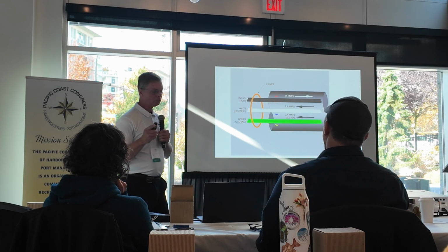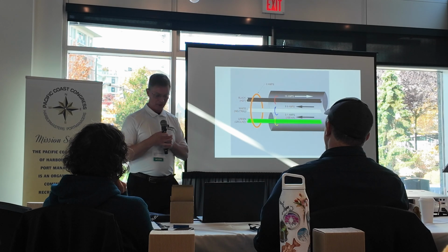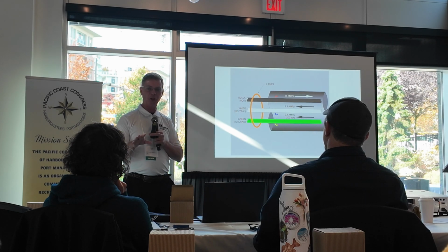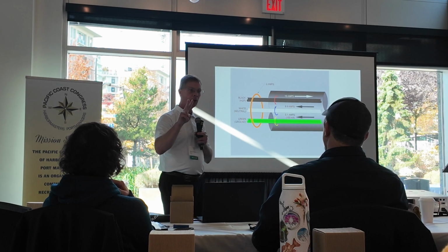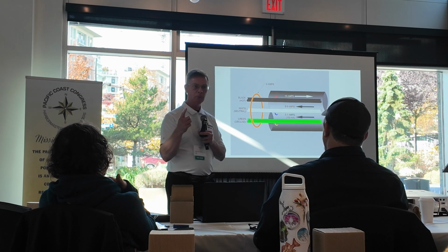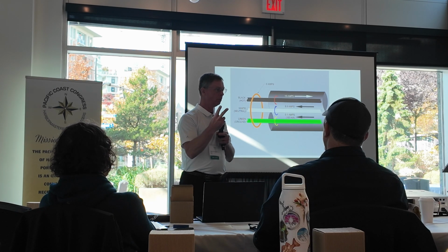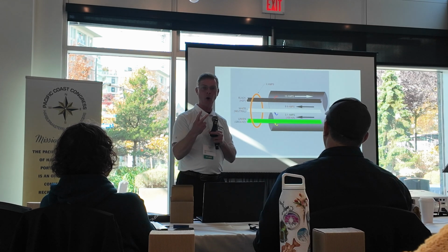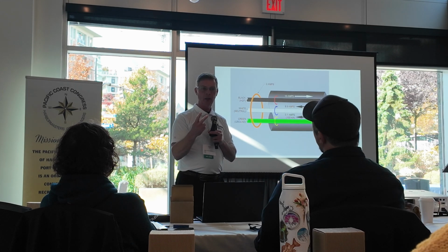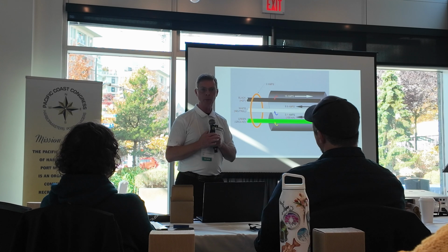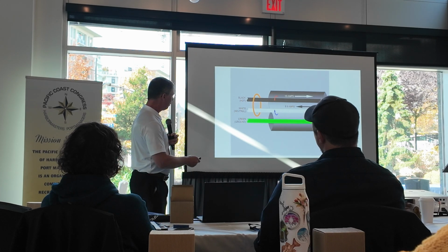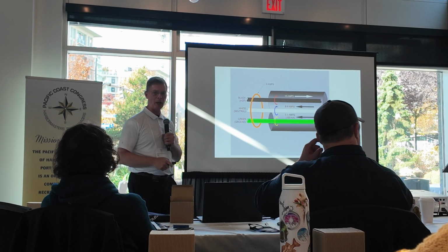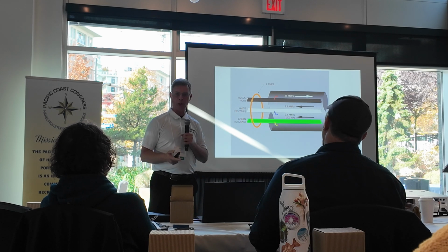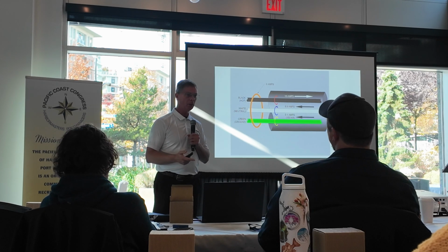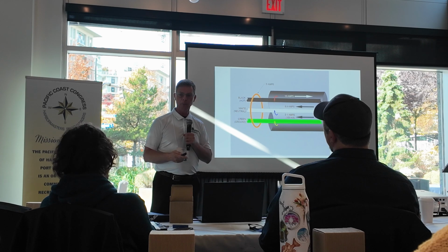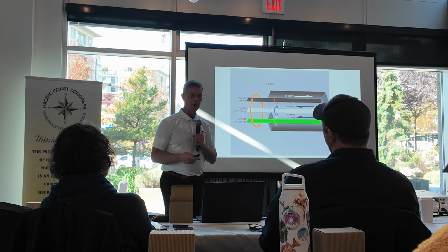Now, look at this. This is not actually accurate, but I teach it this way, that there's 2 types of leakage currents. There's really, really bad leakage current. Then there's lethal leakage currents. Okay? If the current is contained on the cable, that's the best of the 2 scenarios. It's bad because remember, everything that you touch is connected to that green wire. You don't want current going through the metal that you can touch. And that's really, really bad. But generally it's not lethal. Okay? Generally it's not.